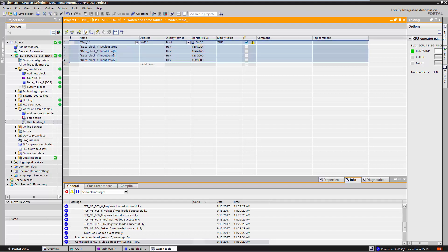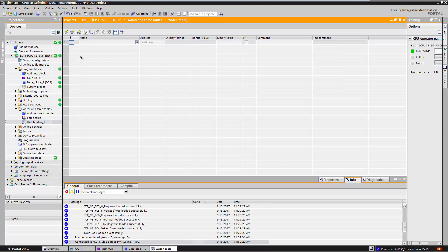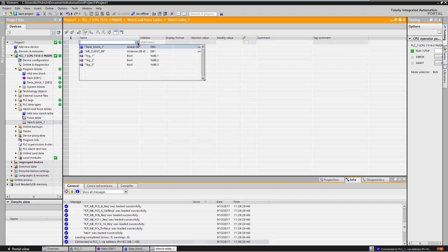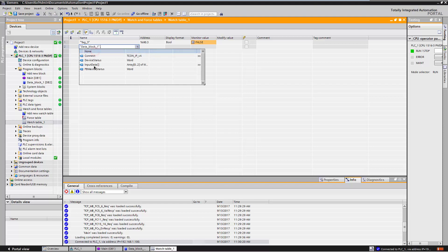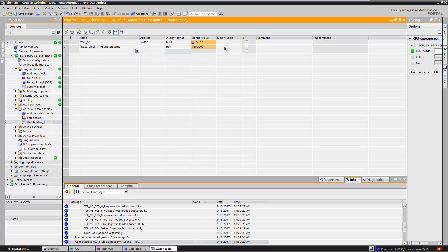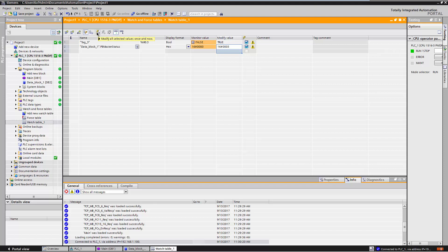Delete all entries. Create an entry for the variable of the input parameter REQ of the instruction that is used to write the Modbus master status. Create another entry for the variable of the Modbus master status. Set the value of the MB Master status variable to 3. This corresponds to Run mode. Set the value of the variable for the REQ input to True. To write the value, click on Modify Now. Now you can see that the value was written.